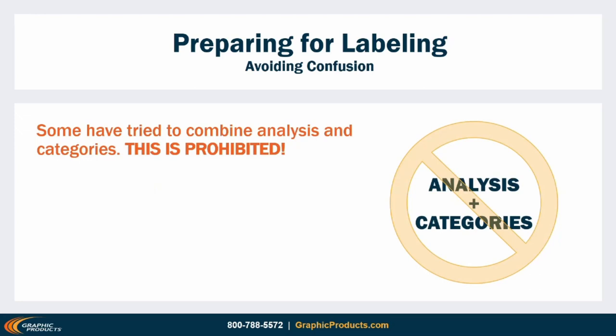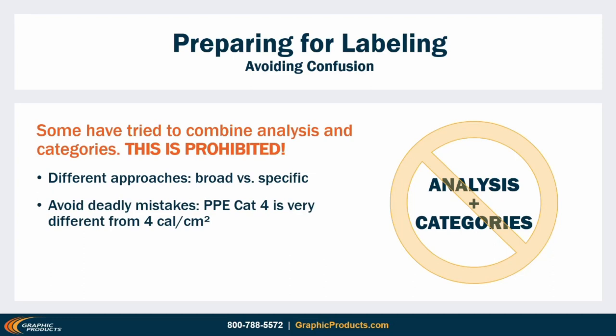In the past, a lot of people tried to use both systems at the same time — calculating the incident energy and then assigning an arc flash PPE category as well. This has been specifically prohibited in NFPA 70E since the 2015 edition. The systems approach their decisions in different ways: PPE categories are based on NFPA's conservative estimates for general scenarios, while incident energy calculations are based on the employer's detailed math for the exact equipment and installation. A PPE category of four means you need an extremely protective space suit; an incident energy of four cal/cm² means you need standard thermal gear and a face shield. A misunderstanding here could be deadly.